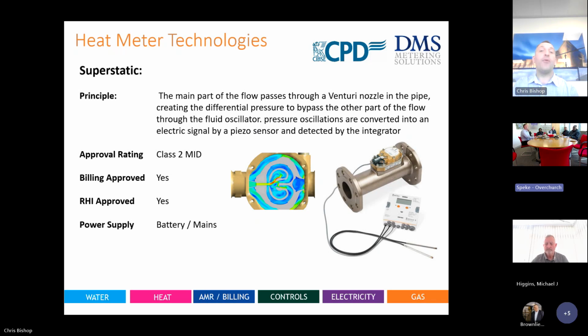How it operates is it's got a small venturi inside. So the flow passes through the chamber of the meter. It causes a slight back pressure. 10% of the flow goes into the superstatic head, which you can see on the drawing there on the right hand side. And then it's 10% linear flow. So the actual pulse goes inside the head, which means 90% of the flow rate does not get seen by the transmitter itself. It's directly proportionate to the flow that's actually being seen by the piezoelectric sensor. So it's basically a vibration inside, very similar to the transit time. It's measuring the velocity or the speed of the pulse inside that then brings that flow rate data back to the main brains of the heat meter.